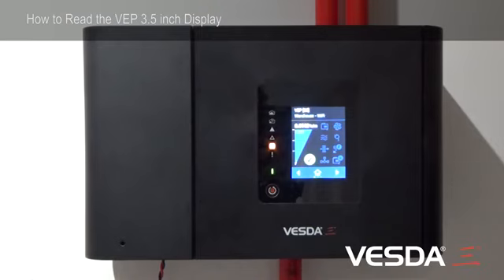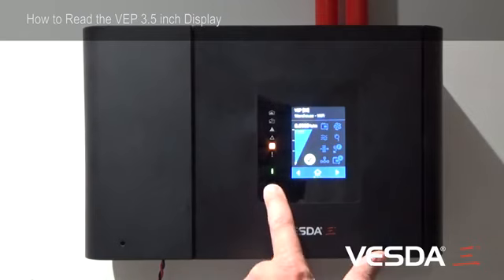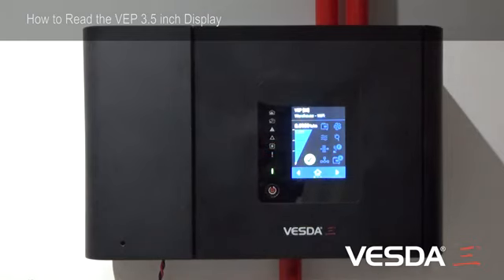To return the detector to normal position, we can hold the button again for a further 4 seconds, at which point the detector has now been restored and it is available to transmit alarms should there be the presence of smoke.